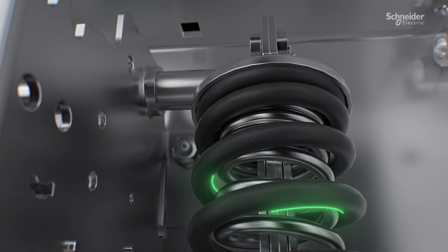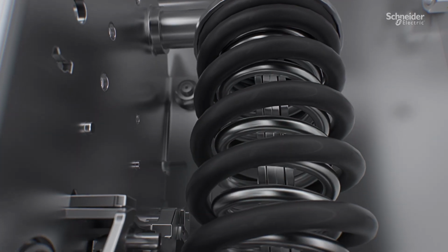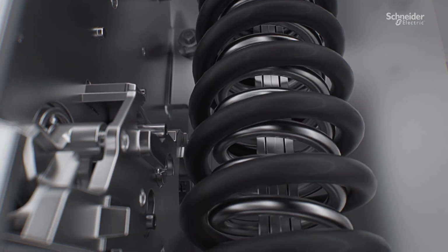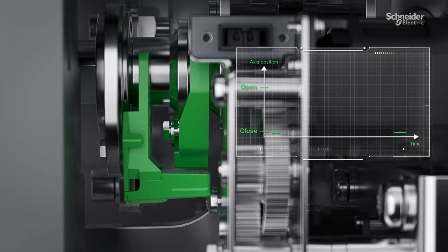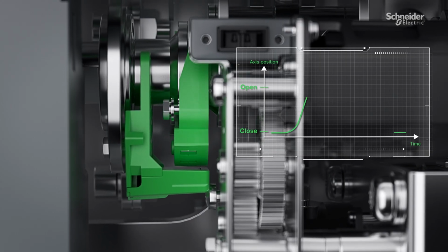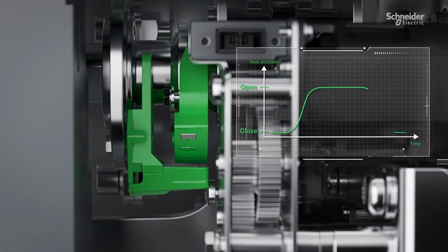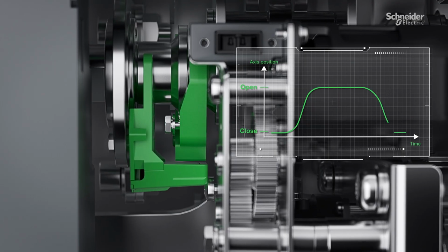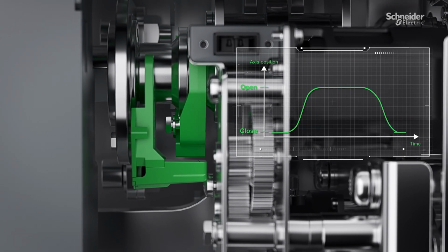Opening a breaker requires rapid deployment of energy from a charged spring. The mechanism must operate precisely to minimize arc energy. A dedicated sensor tracks operating speed, highlighting any decrease which would risk safe and reliable performance.